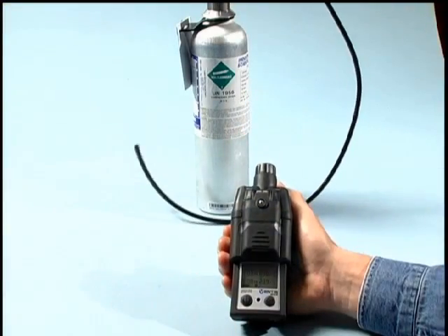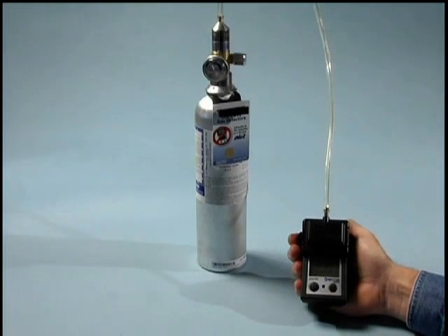For a diffusion Ventis MX4, the user will need to utilize a 1.5 liter per minute fixed flow regulator and the applicable Ventis MX4 calibration cup. Other than that, the procedure is exactly the same.